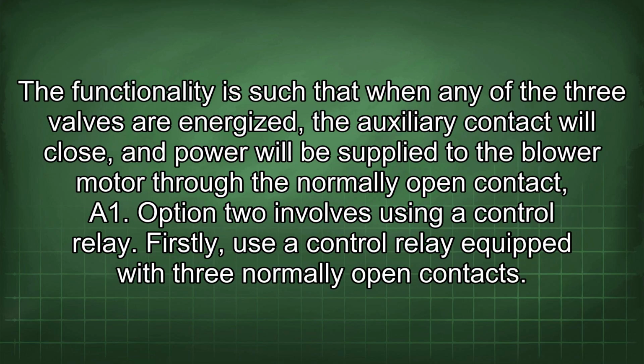The functionality is such that when any of the three valves are energized, the auxiliary contact will close and power will be supplied to the blower motor through the normally open contact A1.